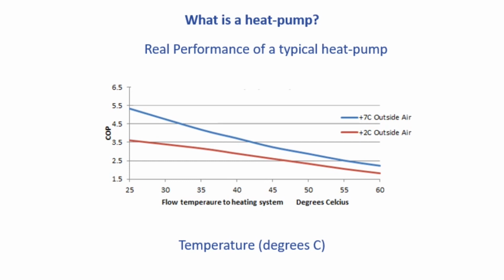In reality, however, the coefficient of performance of a heat pump is quite a bit lower than the theoretical prediction. So, for instance, this graph shows the coefficient of performance for a heat pump. I think it's a Mitsubishi unit, where we're plotting the flow temperature on the bottom axis. So if we're going up to a 50, 60 degree flow temperature, the coefficient of performance, where the outside air is 2 or 7 degrees, is going to be dropping below 2.5 and approaching 1.5. So that's the reality. Still good. I mean, it's still much better than just getting 1 for 1. You're almost doubling the amount of heat for the electric power that you're using in reasonably cool conditions.